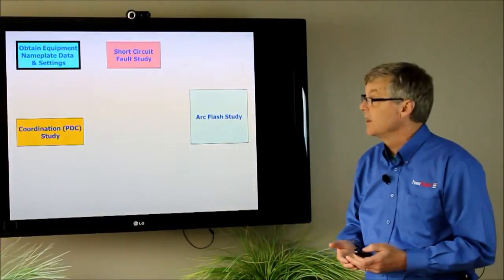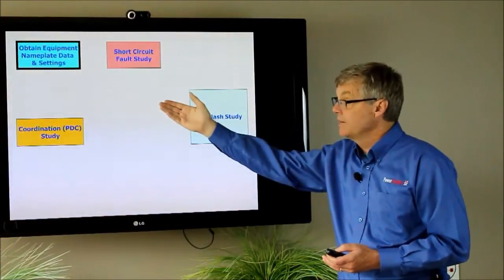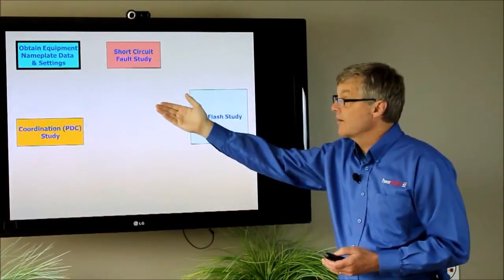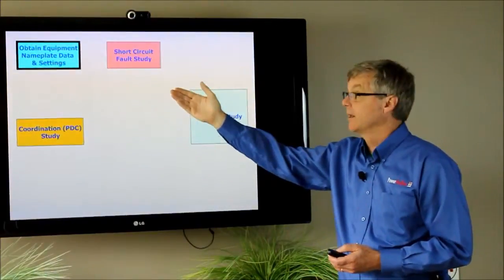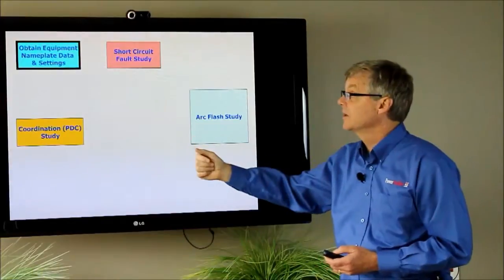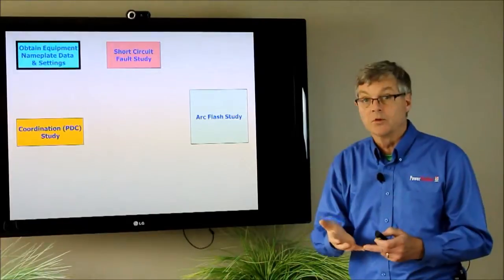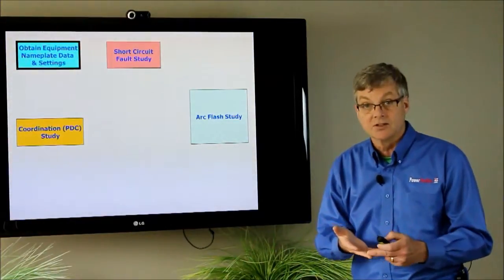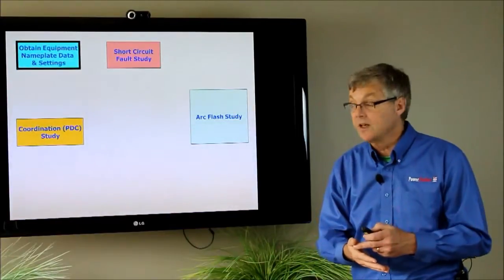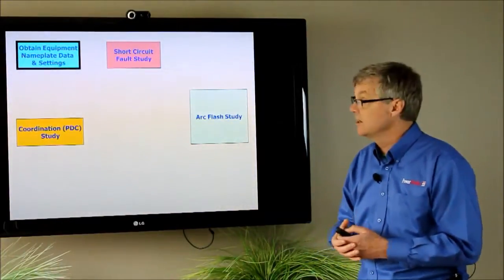What we have to do is go to each piece of electrical equipment and read the nameplate data and also look at the protective devices and get their nameplate data and their protective device settings. We need to know for instance the size of the transformers, the impedances, the conductor sizes, the lengths, the number per phase - all this information needs to be gathered in a detailed fashion.